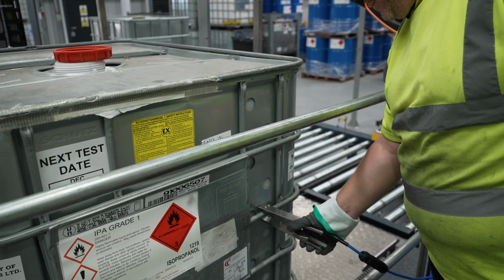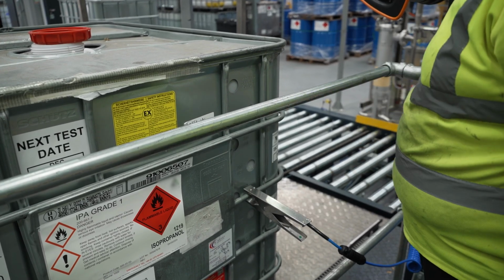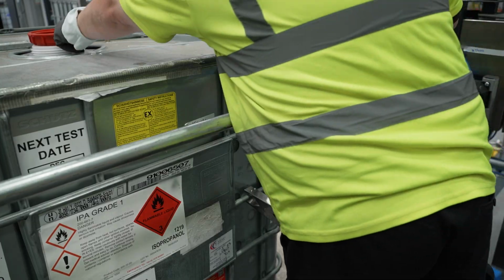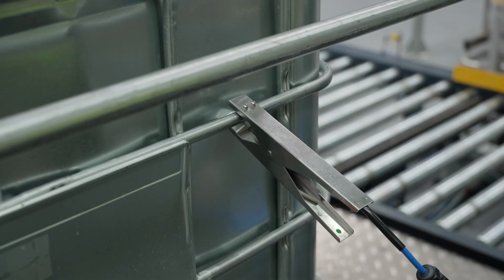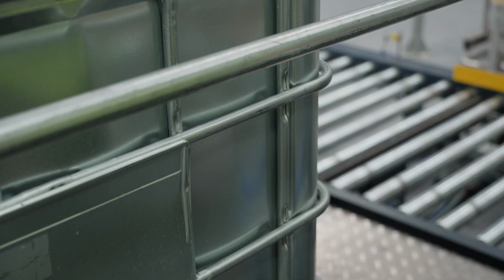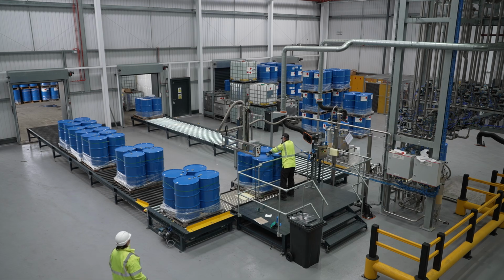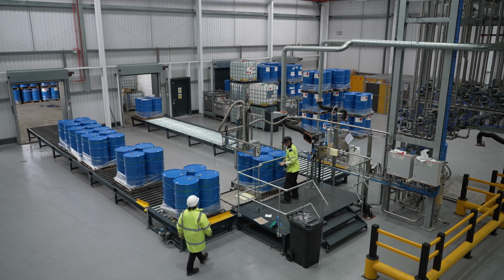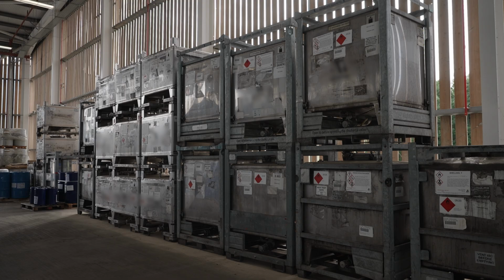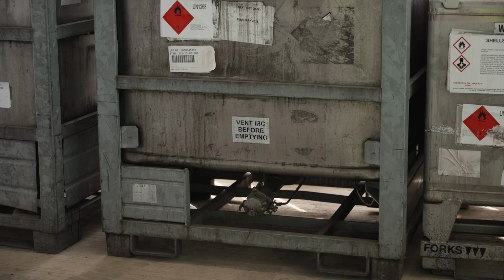When earthing and bonding, it is vitally important that the clamp is in place before filling operations commence and removed when filling is complete. Do not attempt to attach a clamp while filling is in progress, as this has the potential to generate a spark. When using metal IBCs, the frame around the tank may not be bonded to the tank via an earthing strap, and therefore both frame and tank need to be earthed separately.